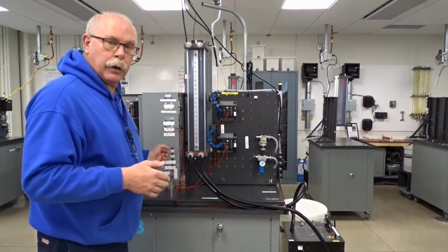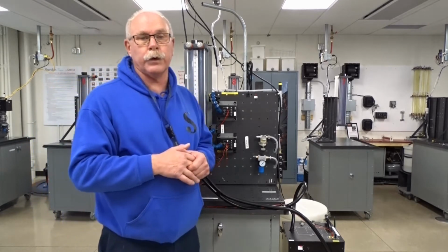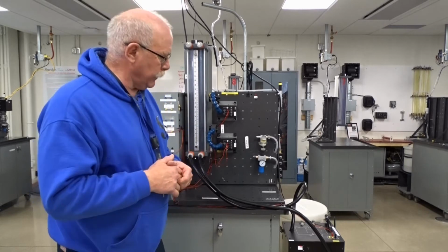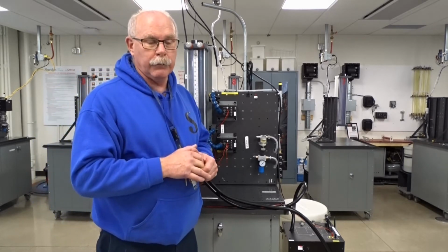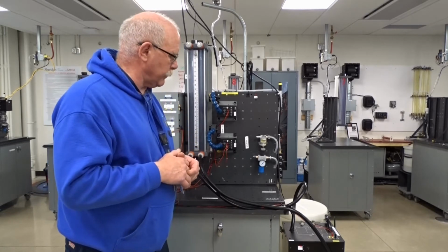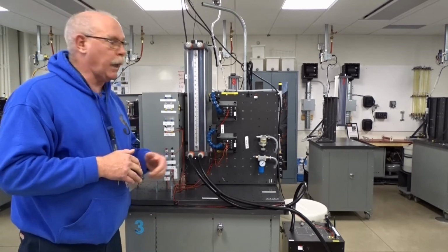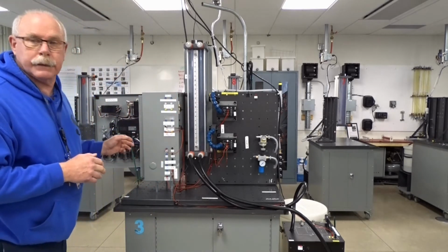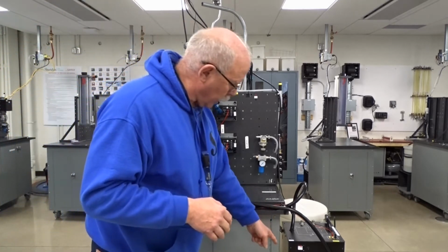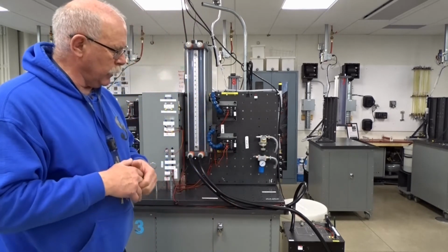What we feed from our control out to our pump is actually a 4 to 20 milliamp signal, which is a standard current instrument signal. It has a span of 16, and it has an offset of 4. Okay, so we have the primary sensing element, the PLC, which is overkill in this box, and then we have a motor pump combination, and that's actually our final element. That's what's doing the work.